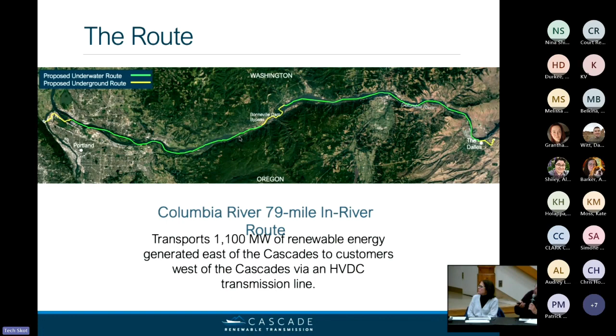We've installed cable in the Raritan River in New Jersey and gone through the Atlantic Ocean to come up into Long Island in New York. And then down in this end, down in Portland, we will come ashore at Hayden Island. From there, we will find our cable's way across into the converter station located in the Rivergate Industrial Complex. From there, we can reconvert it back to 230,000 volts AC and connect to the PGE Harborton substation.